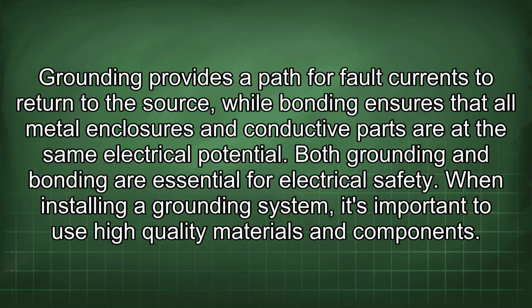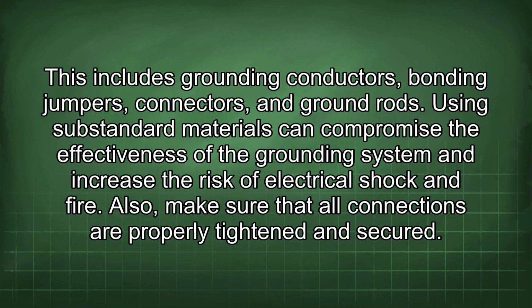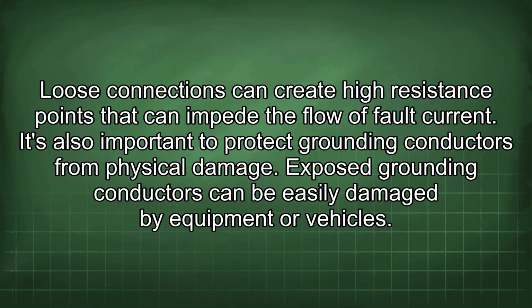When installing a grounding system, it's important to use high-quality materials and components. This includes grounding conductors, bonding jumpers, connectors, and ground rods. Using substandard materials can compromise the effectiveness of the grounding system and increase the risk of electrical shock and fire. Also, make sure that all connections are properly tightened and secured. Loose connections can create high resistance points that can impede the flow of fault current.